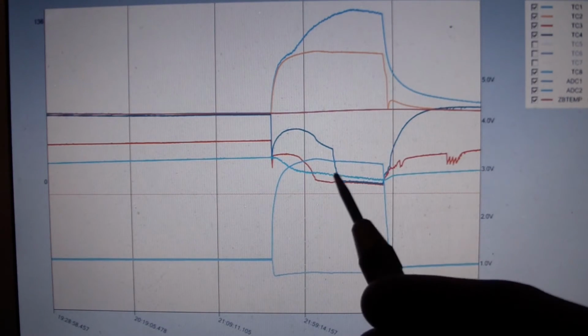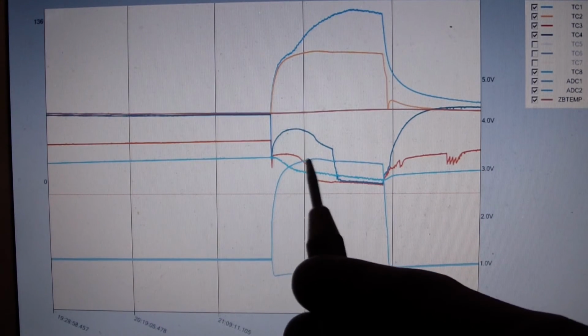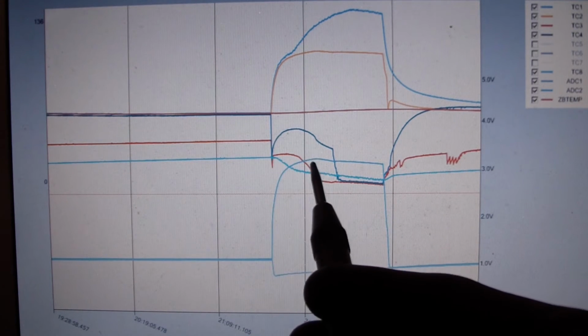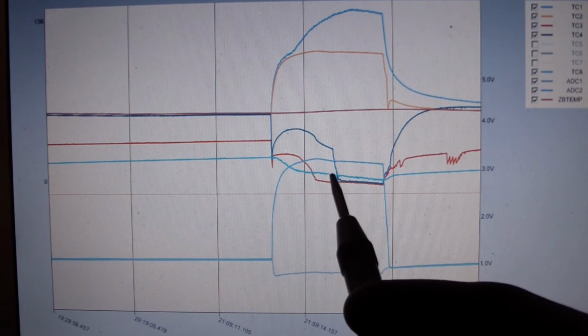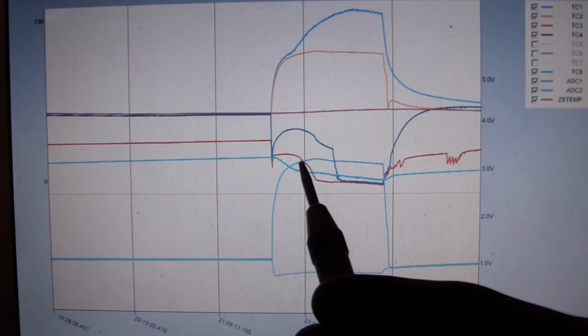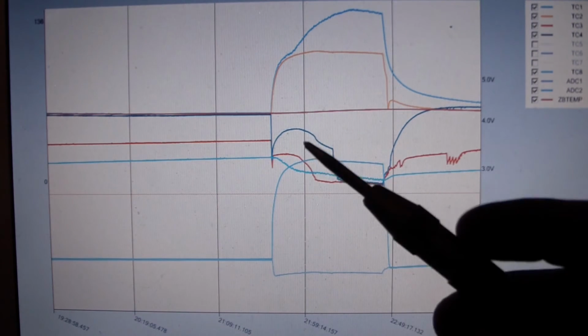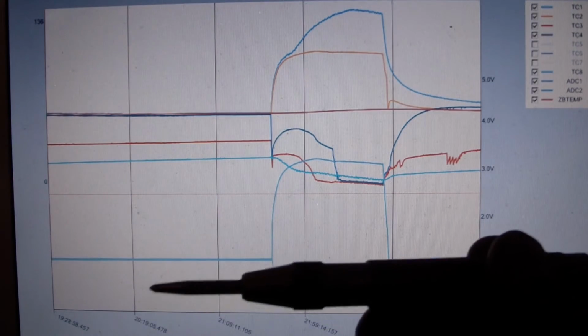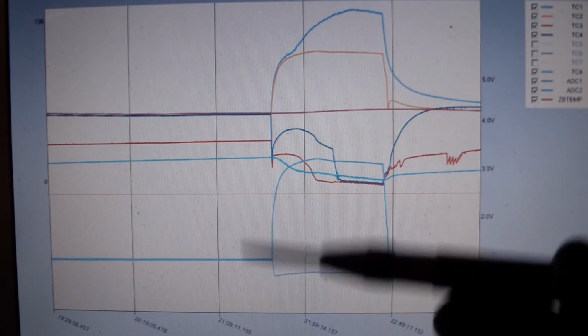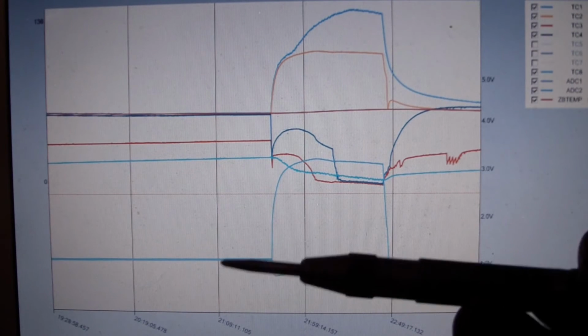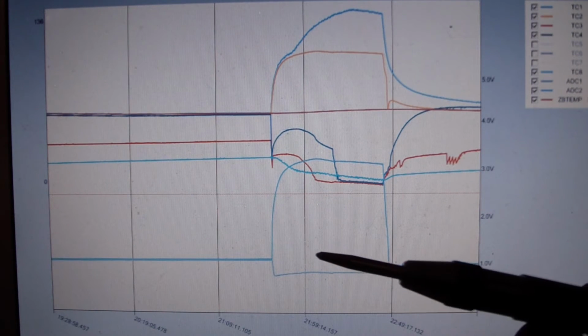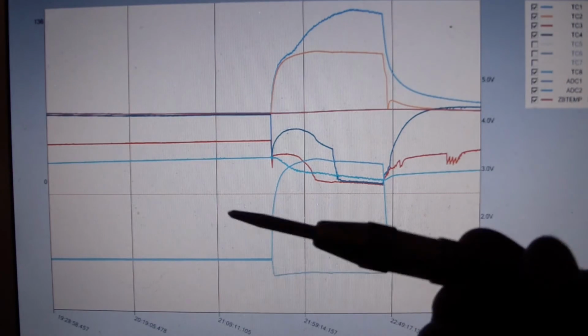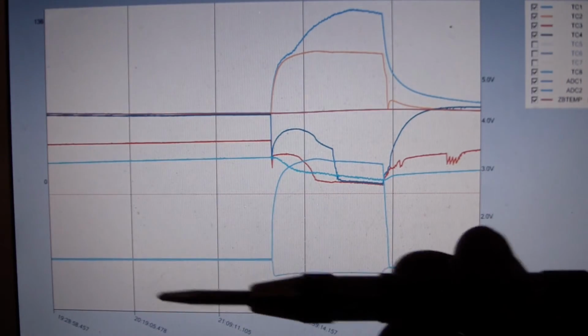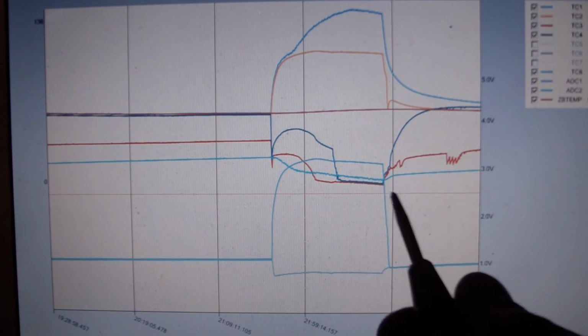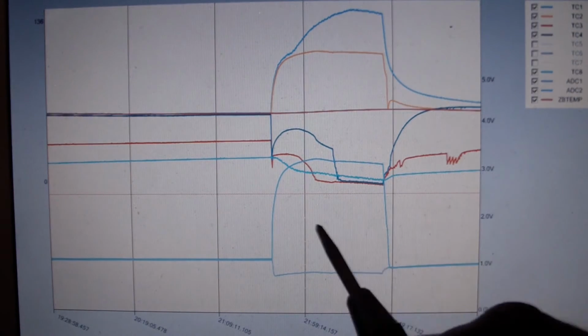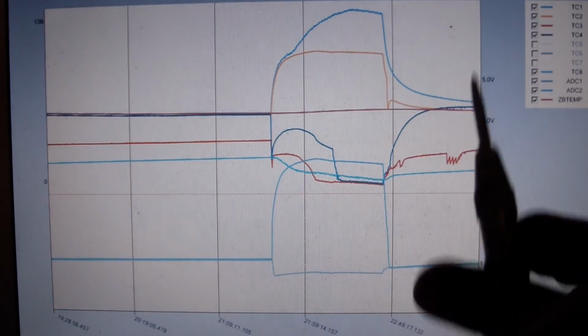So if this system as it stands right now, if I were to add some extra refrigerant charge to it, I could get this to drop to saturation much more quickly. However, it's going to raise the head pressure as well. Because at certain points in the runtime, that liquid is eventually going to start to back up into the high side, and I might get a little bit better subcooling, relatively speaking. But the head pressure has risen as well, so the condensation pressure has risen in the high side. So I haven't really done myself any service. Eventually, that head pressure rises and forces more liquid through the capillary tube and better supplies the evaporator, but I have to think about overall system performance and amperage draw on the compressor and discharge superheat and things like that.